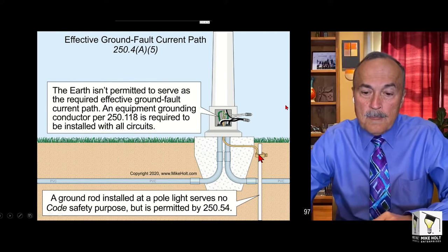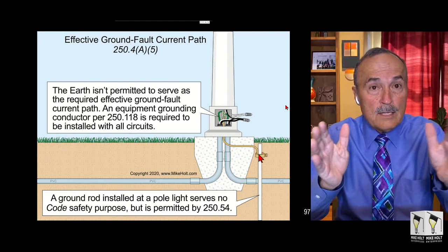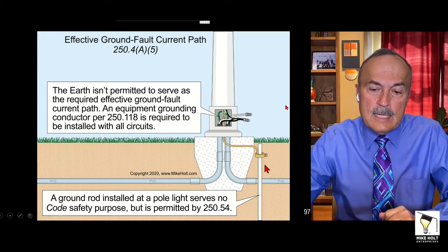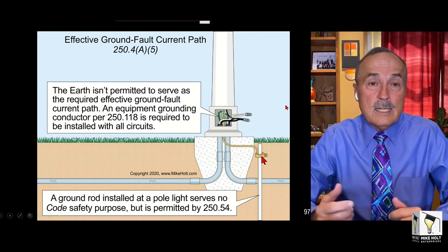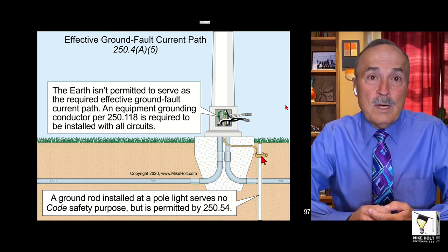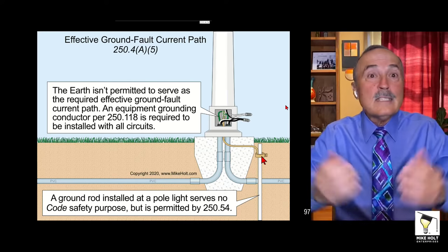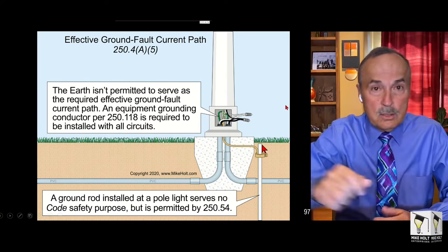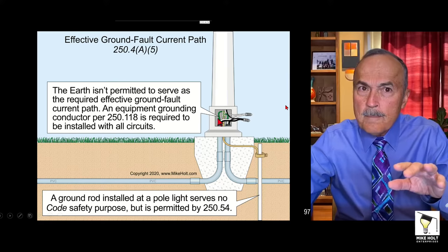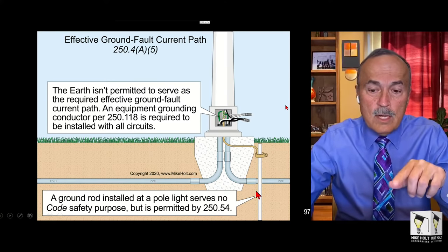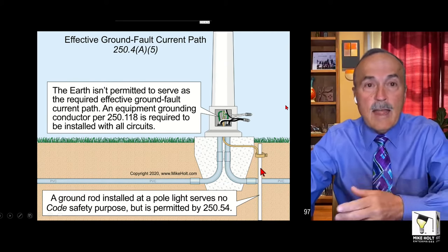The code says about that auxiliary electrode: you don't have to bond it in accordance with 250-50 (bonding all electrodes together). And it says it doesn't matter what the resistance is of that electrode - it could be 1,000 ohms or 100 ohms. You could drive a 16-penny nail if you want for your electrode. You can take an 8-foot or 10-foot ground rod, cut it in thirds or half - it doesn't matter. The code doesn't even care what size wire you run to the auxiliary electrode - all covered in 250-54.